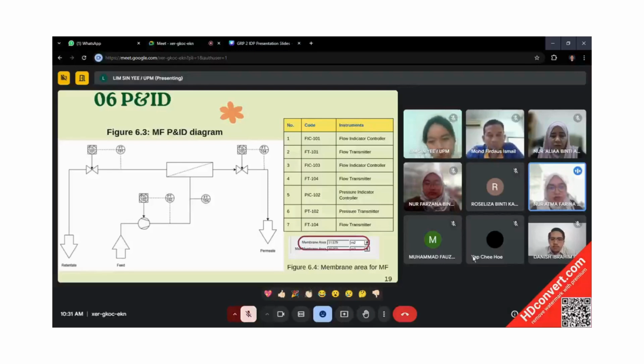The retentate, which contains fiber that is rejected by the membrane, flows out of the system, and its flow rate is indirectly controlled by feed pressure and system dynamics. The permeate, which is the filtered soy milk, will pass through the membrane and is monitored by flow transmitter FT104 and regulated by flow indicator controller FIC103 before being sent for further processing, which is the enzyme step.